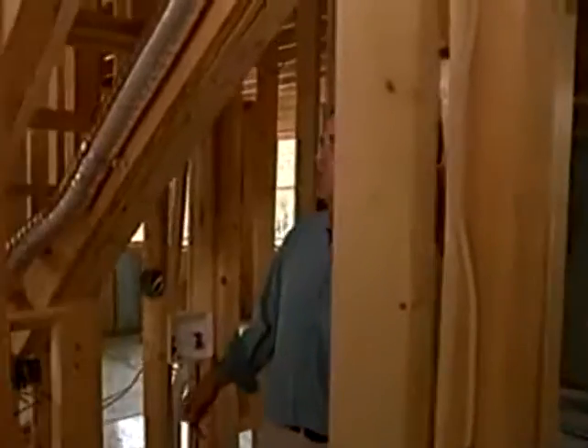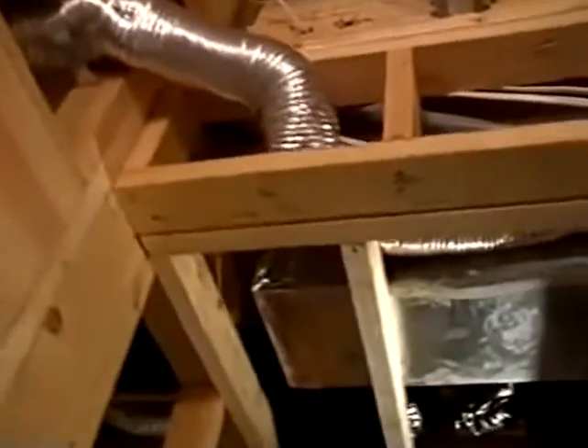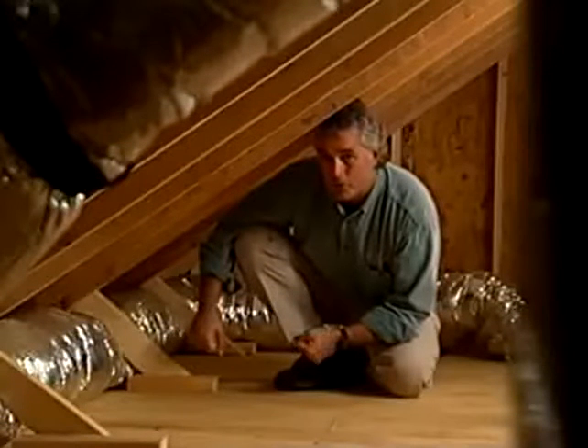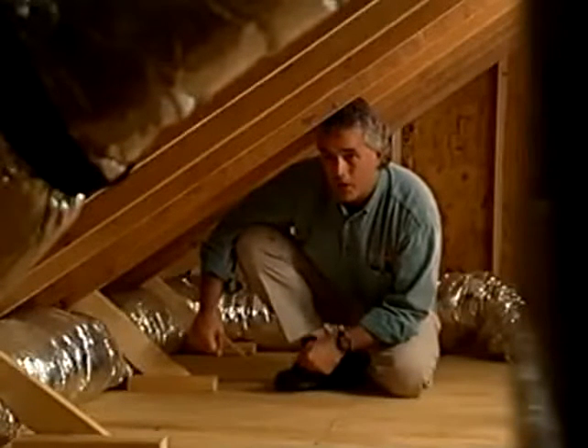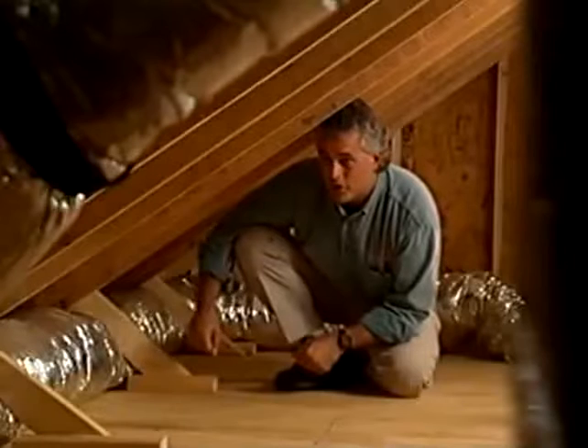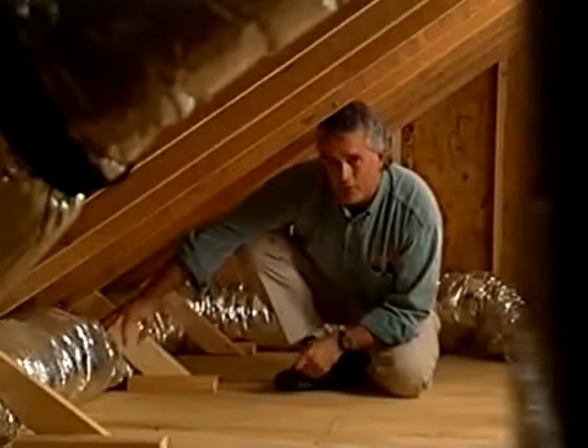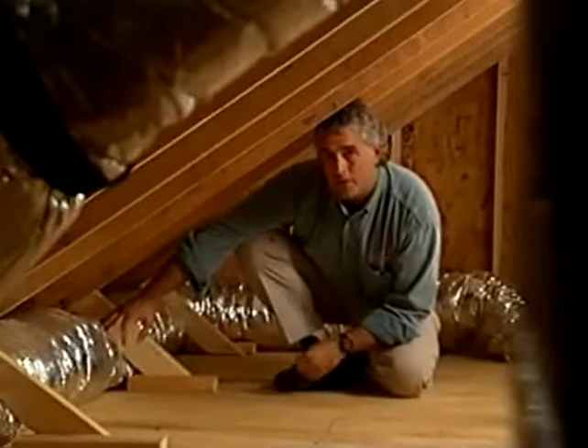Whenever we're installing ductwork, whether it be for heating and air conditioning equipment or for an exhaust appliance, we want to keep our ductwork in as straight a line as possible, because we know that each turn in the ductwork can create restriction in the airflow, and restricted airflow has a negative impact on the performance of the equipment. We're in the knee wall area of this home. This knee wall area will be used as a storage closet by the homeowner. The HVAC contractor has done a good job of putting the ductwork as far out of the way as possible. This will maximize the storage.